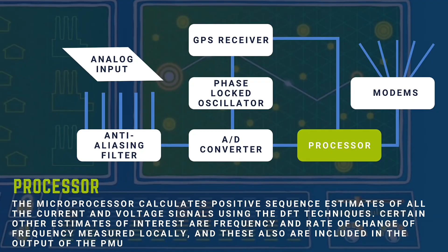Processor: The microprocessor calculates positive sequence estimates of all the current and voltage signals using DFT techniques. Other estimates of interest are frequency and rate of change of frequency measured locally, and these are also included in the output of the PMU.